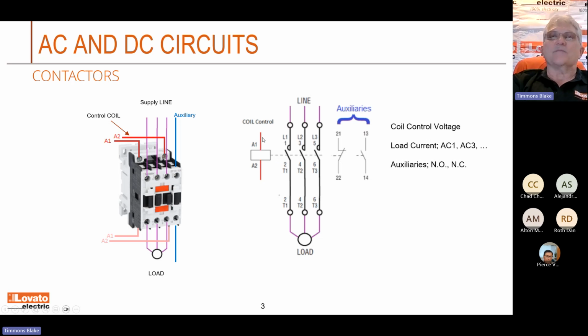It's typical that when you get one of these contactors, you're going to see an A1 and an A2 on there. Pretty much every contactor I've ever seen has the A1 and the A2 for the coil, so keep that in mind. Also, in addition to the contactor, you'll have some internal auxiliary contacts. I've got a picture of a normally closed one and a picture of a normally open one. You can have either or both on those contactors.